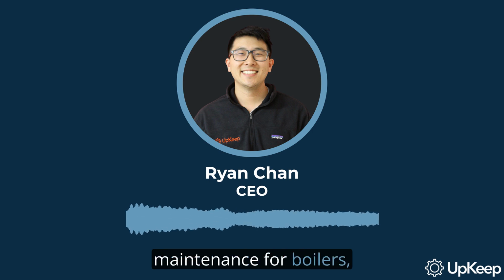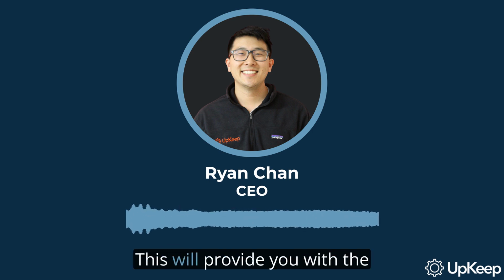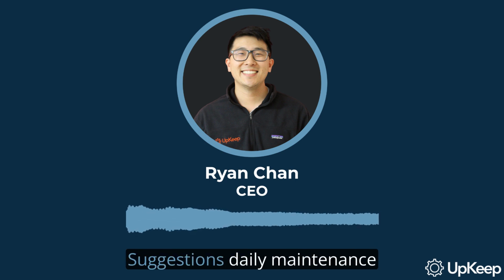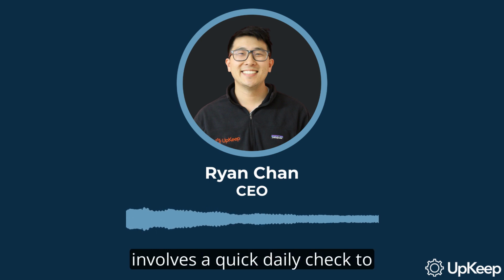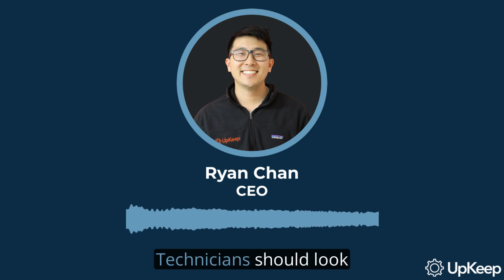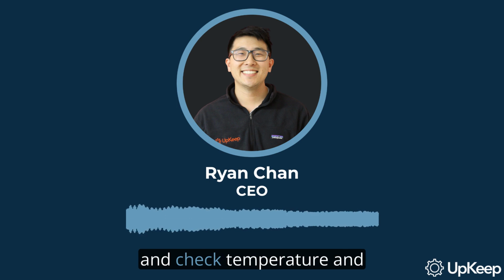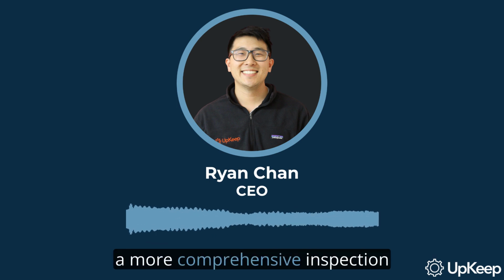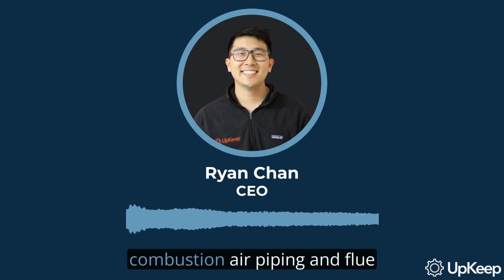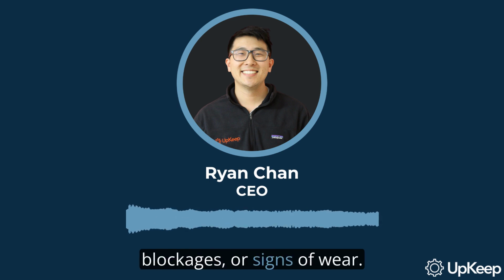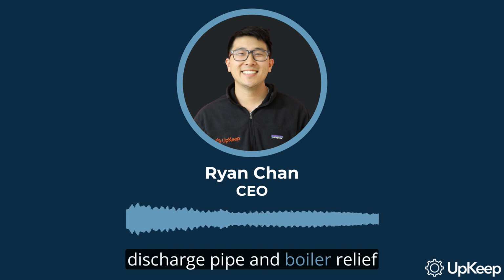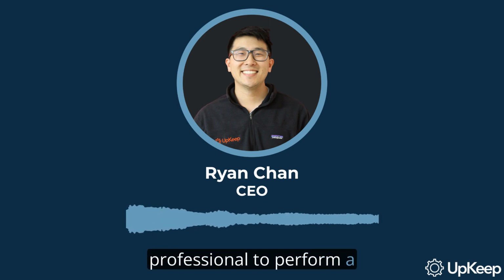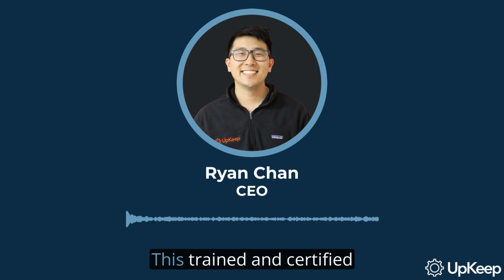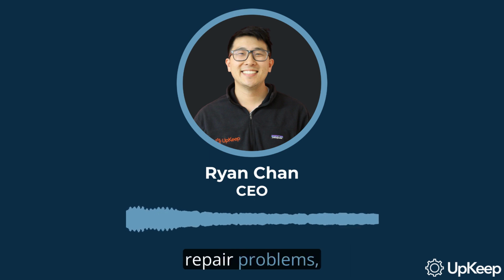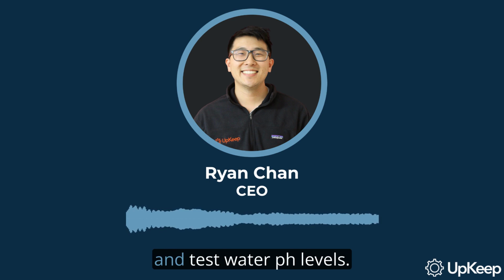When it comes to preventive maintenance for boilers, the first place you want to start is with your owner's manual. This will provide you with the manufacturer's recommended maintenance plan and upkeep suggestions. Daily maintenance involves a quick daily check to spot potential problems before they become major ones. Technicians should look for leaking water, unusual noises, or obstructions, and check temperature and pressure readings. Each month, a more comprehensive inspection should be performed. This includes checking the combustion air piping and flue gas vent piping for leaks, blockages, or signs of wear. Also, check the relief valve discharge pipe and boiler relief valve for leaks, and look for blockages in the drainage system and lines. Once a year, bring in a licensed service professional to perform a complete inspection and conduct annual maintenance work. This trained and certified technician should rigorously test the boiler and repair problems, clean the heat exchanger, check connections and wiring, and test water pH levels.